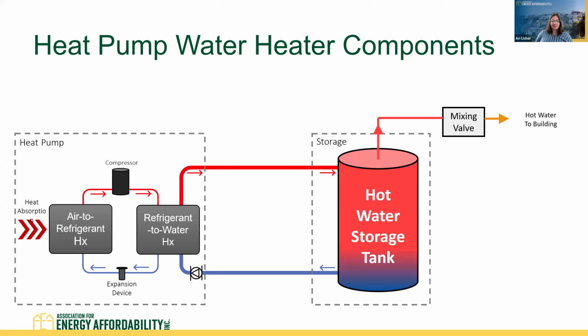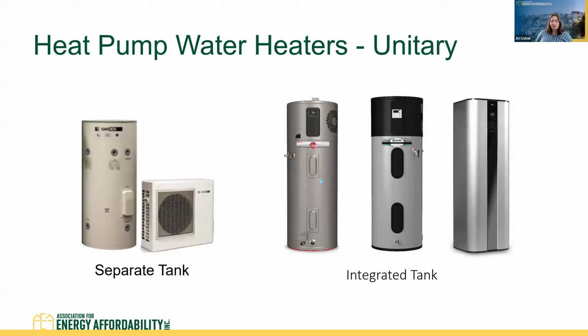Storing water at a high temperature, upwards of 140, is definitely suggested. A mixing valve should always be included in a heat pump water heating system. That mixing valve then mixes that hot water down to the delivery temperature, usually around 120, and delivers hot water to the end use. Some different configurations and options.